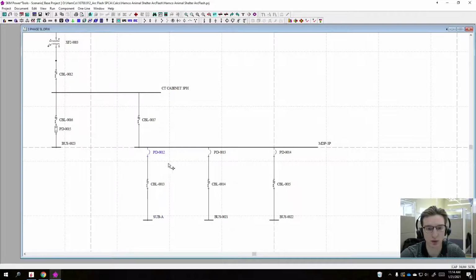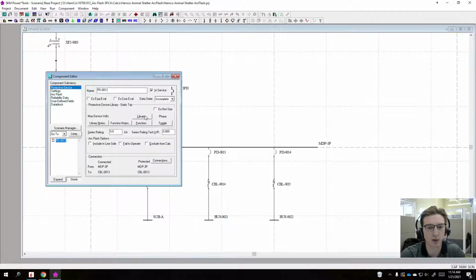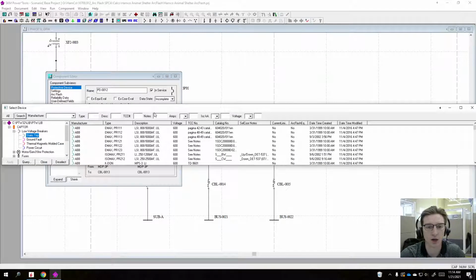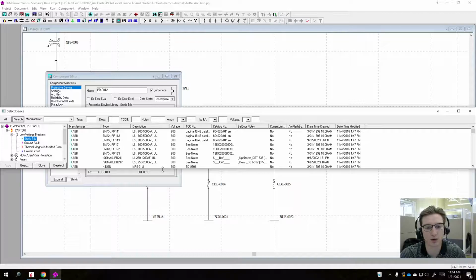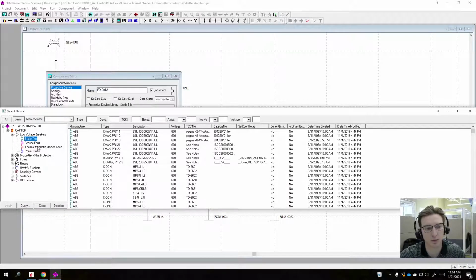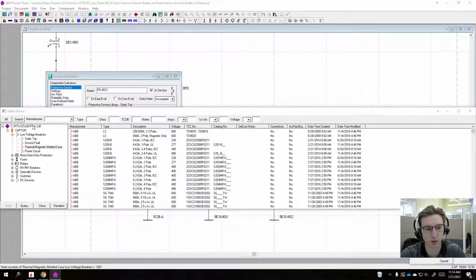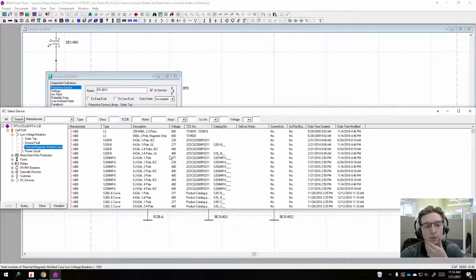So we'll just double click on our breaker here, and we're going to hit library. It's going to load up the library devices. This is a 60 amp breaker, so it's going to be thermal-magnetic. So make sure that in the low voltage breaker settings here, you pick thermal-magnetic, not the static, not the ground fault. You can go ahead and sort by manufacturers.